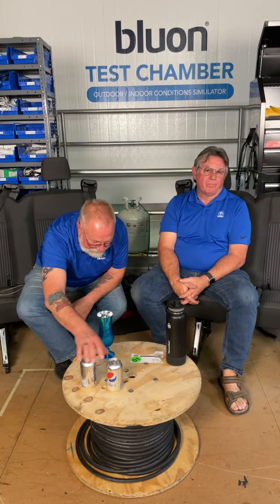But no, seriously, break some of this stuff down into its simple components. If you've got a compressor that's not starting, don't go look at the air handler. The indoor fan, that's not your problem. So zero in on the area you're having the problem and start looking at things that can affect it. One of the things that we ran into a lot with defrost control boards is they can't get something to work. Defrost control boards, you've got low pressure switches tied into them, high pressure switches tied into them. You've got a coil sensor temperature, an outdoor air temperature sensor. You could have a defrost thermostat of some type. So you've got 5 things tying into that board. That could be the problem, and it's not the board.